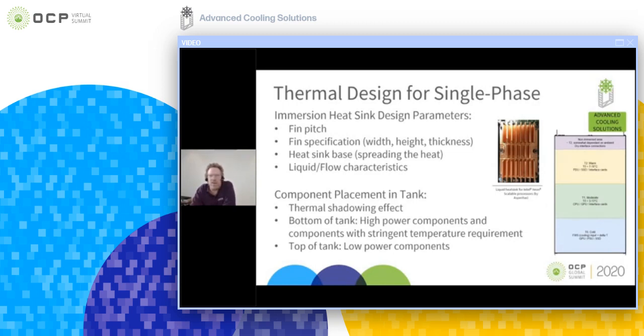There's also a temperature gradient running through a vertical oriented chassis inside an open bath single phase immersion technology. The lowest point in the bath will usually have the lowest temperature, whereas the highest point in the liquid will carry the highest temperature. Simply put, warm liquid wants to move upwards. That means that highest powered components or components with very stringent temperature requirements should be placed deeper into the liquid and therefore more towards the rear of the chassis. Whereas high temperature tolerance components or components with only minimal thermal properties are usually safe to place in the upper side of a chassis, more towards the front.